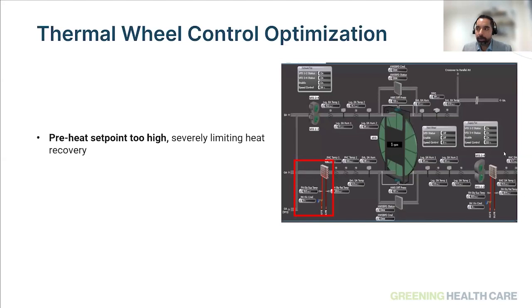Generally, in most cases, if these are enthalpy wheels, they should be sized and selected for around -15 to -16 degrees C incoming air temperatures. And if the set point on the preheat is higher by 0, 5, or 10 degrees C, then there's an opportunity to optimize these wheels. And that is as simple as updating the control sequence to change that set point to a higher or lower set point.